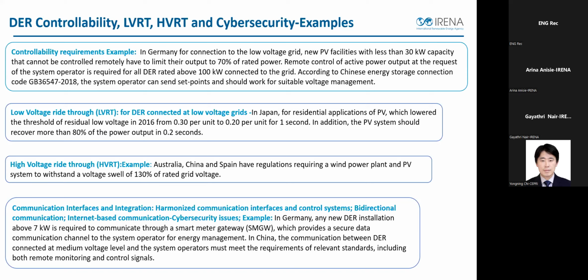One is from Germany, where PV facilities of less than 30 kilowatt capacity that are not controllable need to limit their output to 70% if they are not connected and not controllable. Then regarding low voltage ride-through, like I mentioned before, it was not specified for low voltage grids earlier, but now it's also coming up here. And some of the grid codes that have actually cited this are the German grid code and the Japanese grid code. Then high voltage ride-through, like the speaker earlier mentioned, has had comparatively less emphasis in the grid codes, but now that is also coming up. Australia, China, and Spain have the most stringent regulations and have a grid code specification to withstand a voltage rise of almost 130%. So this is basically to determine the performance of the generator during faults, and it also specifies the tripping voltage threshold and clearing time, and it basically indicates how robust the system is with the distributed resources.